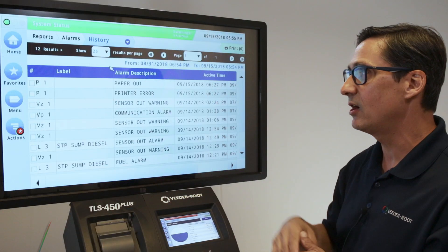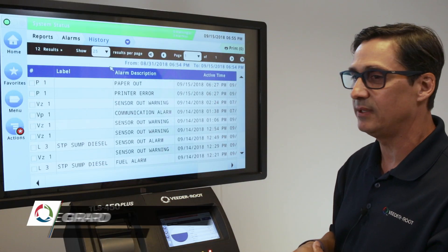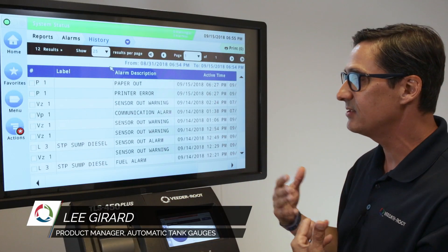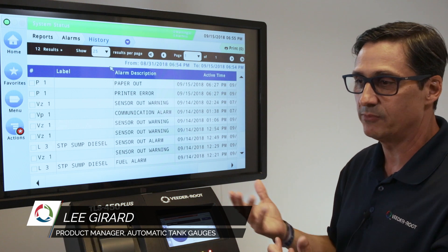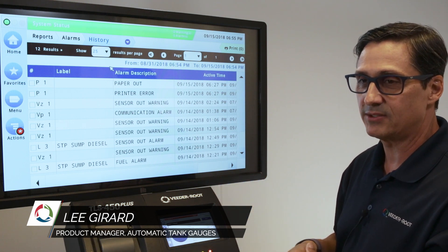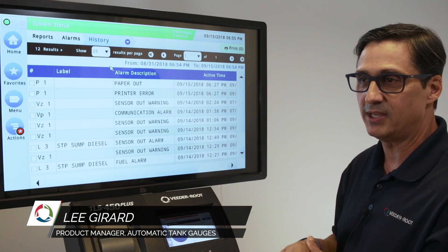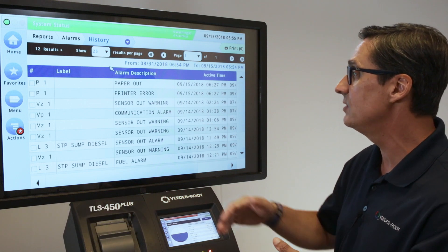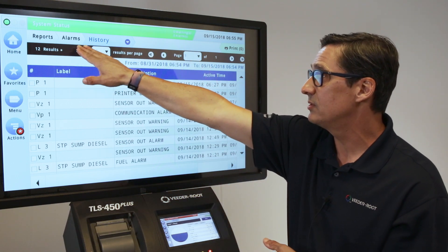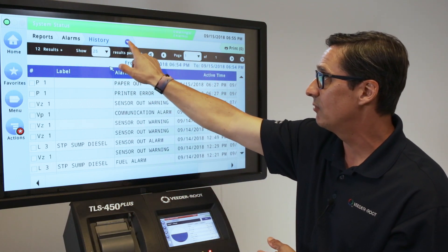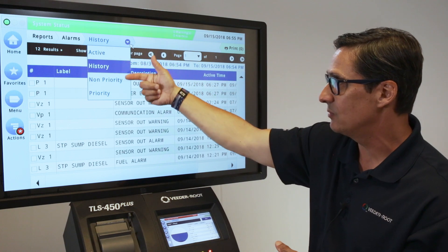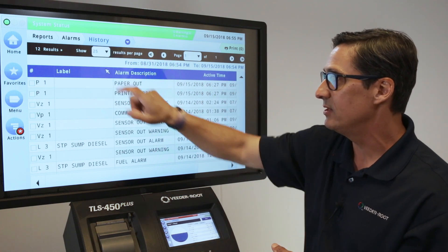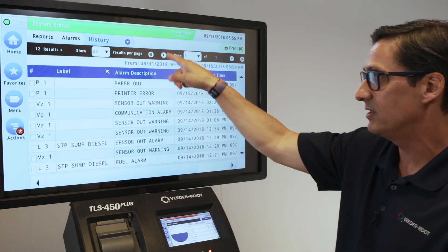Thank you for joining us. We still want to talk about alarms and how to get those alarms out of the system so you can use them for your business practices, such as when you get inspected by a regulatory agency. Under Reports > Alarms in the breadcrumb, you can select active, history, non-priority, and priority. The one that the regulatory agency is going to look for is history.